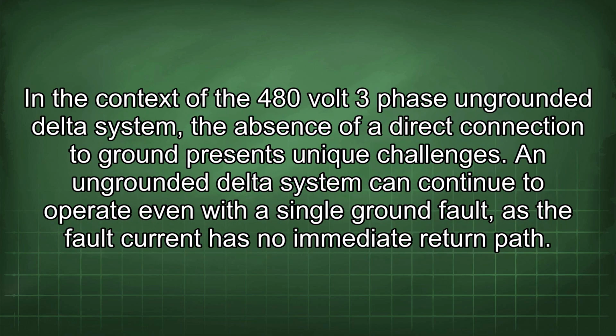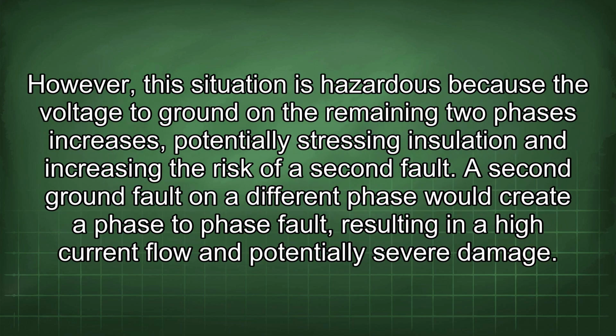In the context of the 480-volt three-phase ungrounded delta system, the absence of a direct connection to ground presents unique challenges. An ungrounded delta system can continue to operate even with a single ground fault, as the fault current has no immediate return path. However, this situation is hazardous because the voltage to ground in the remaining two phases increases, potentially stressing insulation and increasing the risk of a second fault.